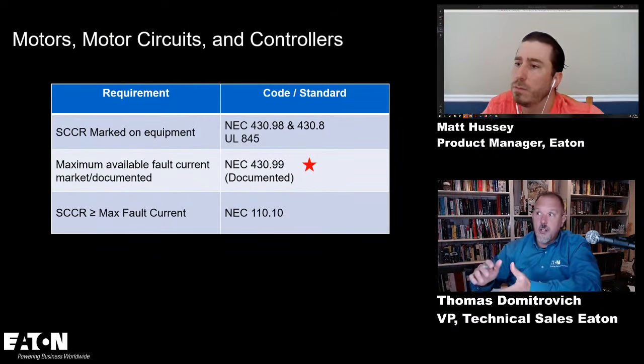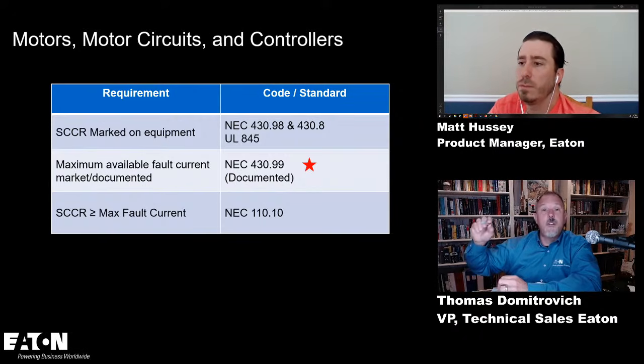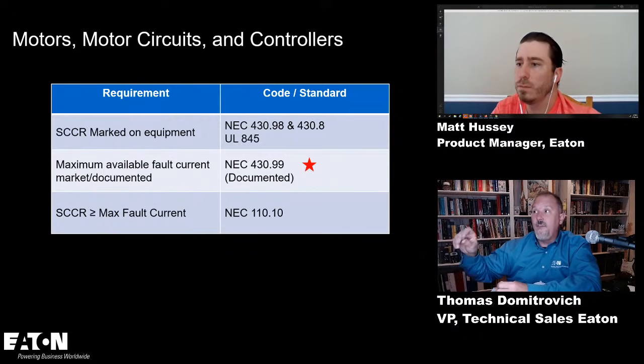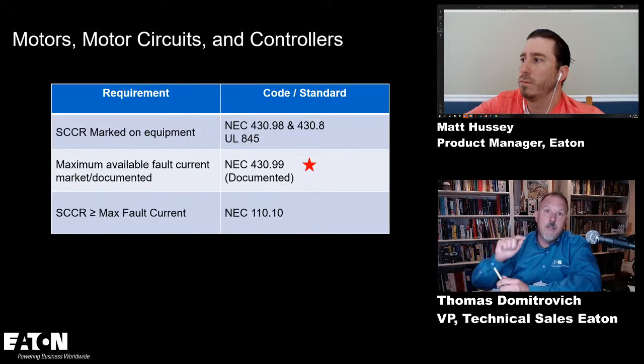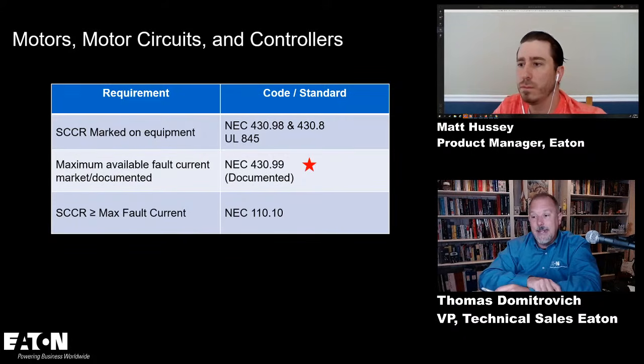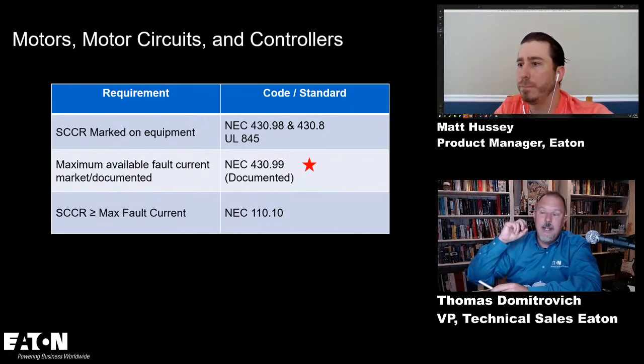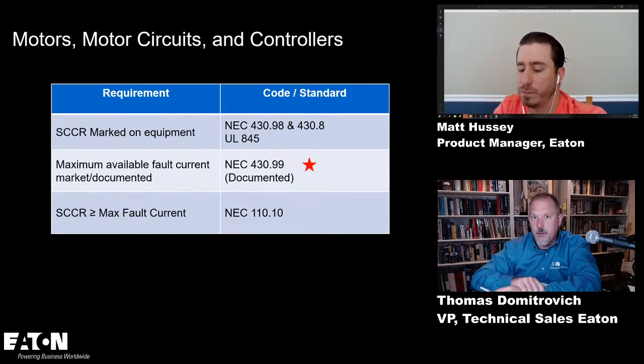The short circuit current ratings are required to be marked on the equipment based on UL 845, NEC 430.98, and 430.8. So if you look in 430, you'll have the marking requirements for motor control centers. And you have to document the maximum available fault current at that motor control center based upon 430.99. You don't have to mark it there. You have to at least have that available fault current documented and available to the AHJ.